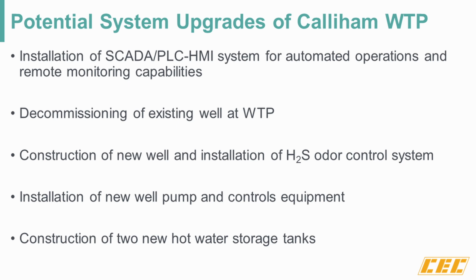So the groundwater in McMullen County could be around 150 degrees Fahrenheit. So it's coming out a little bit spicy there. So we need to have a hot water tank to be able to hold it. We're also going to be adding pumps for the transfer of the hot water to a new cooling tower. And the existing concrete ground storage tanks will also be demolished and replaced to store the cooled water after it's transferred from the cooling tower.